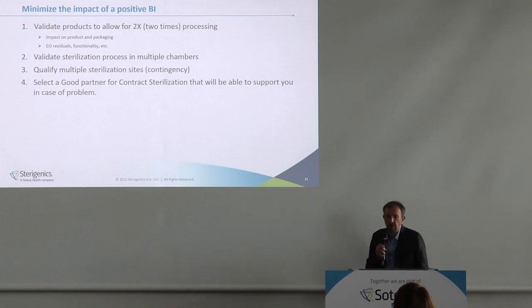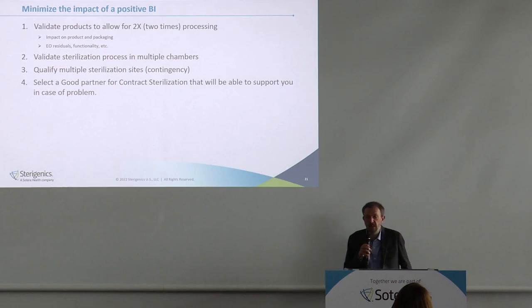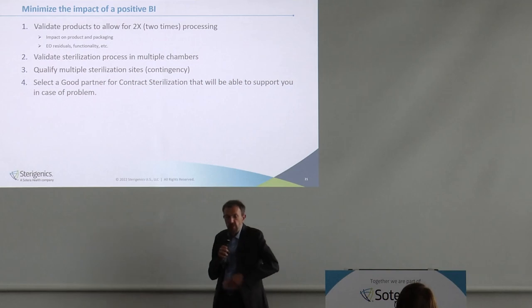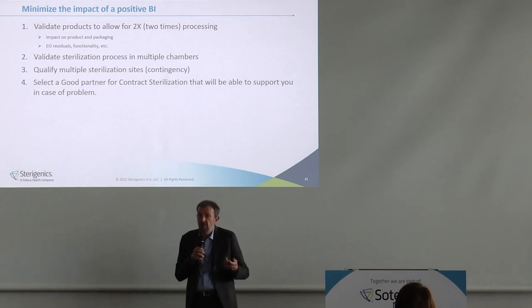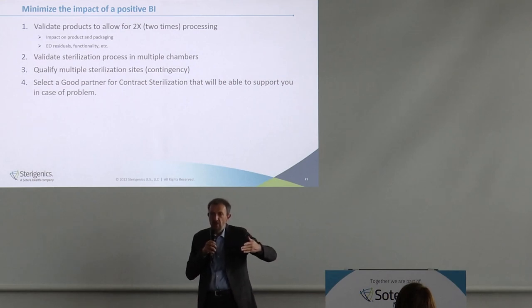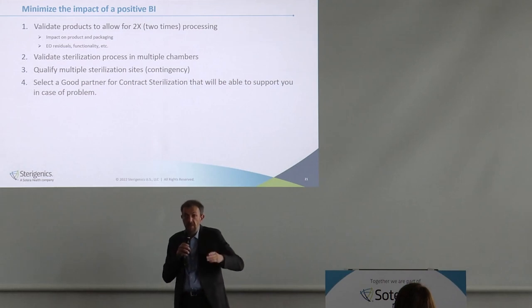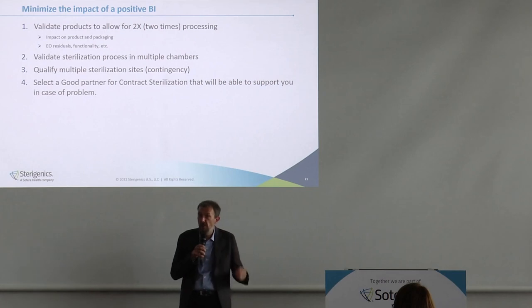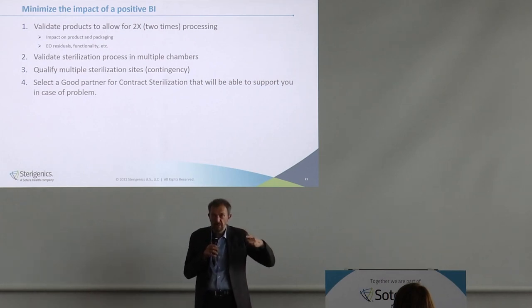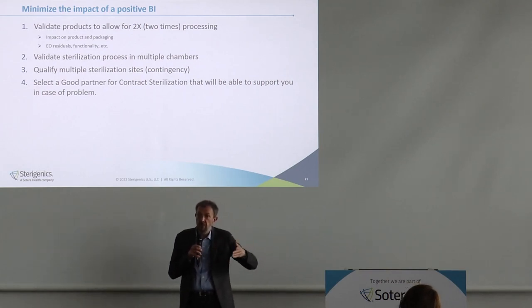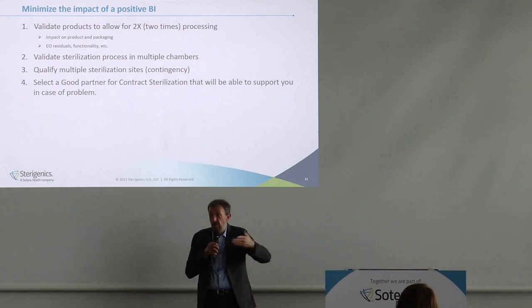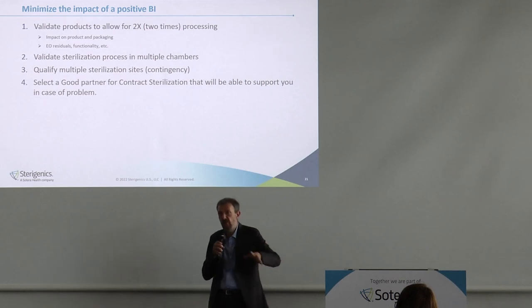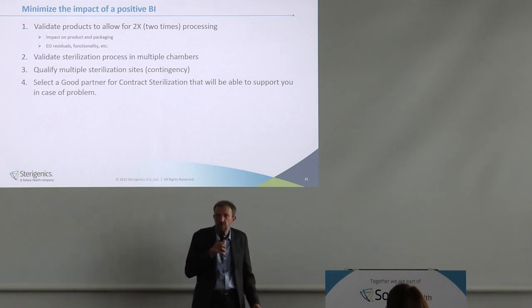To minimize the impact, validating products for reprocessing at least a second time is really key. This doesn't just mean running them twice — you need to assess packaging, cytotoxicity, and biocompatibility after two processing cycles because EO is toxic to cells. You may still pass ISO 10993-7 limits but have an impact on ISO 10993-5 data. Consider doing this validation upfront when starting activities, and have a real partnership with your contract supplier and laboratory — as Nelson Labs and Sterigenics presenting together, we can help you find the best solution.